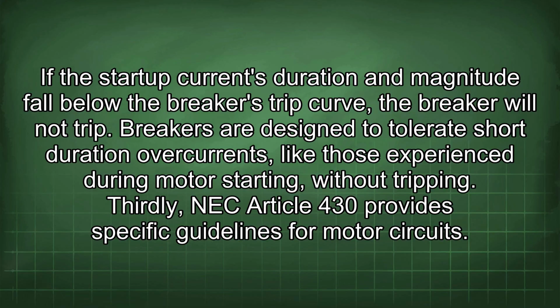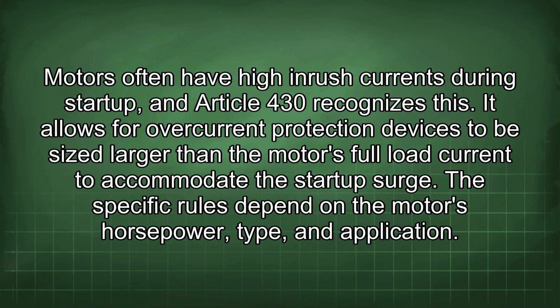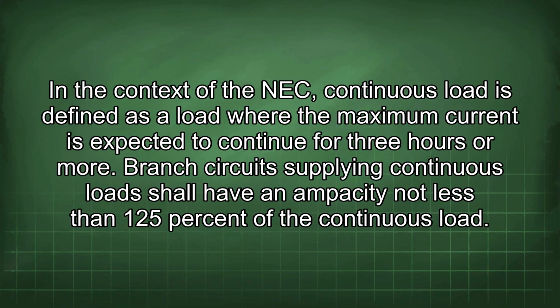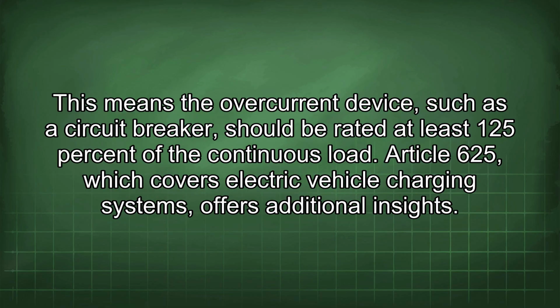Thirdly, NEC Article 430 provides specific guidelines for motor circuits. Motors often have high inrush currents during startup, and Article 430 recognizes this. It allows for overcurrent protection devices to be sized larger than the motor's full load current to accommodate the startup surge. The specific rules depend on the motor's horsepower, type, and application. In the context of the NEC, continuous load is defined as a load where the maximum current is expected to continue for 3 hours or more. Branch circuits supplying continuous load shall have an ampacity not less than 125% of the continuous load. This means the overcurrent device, such as a circuit breaker, should be rated at least 125% of the continuous load.